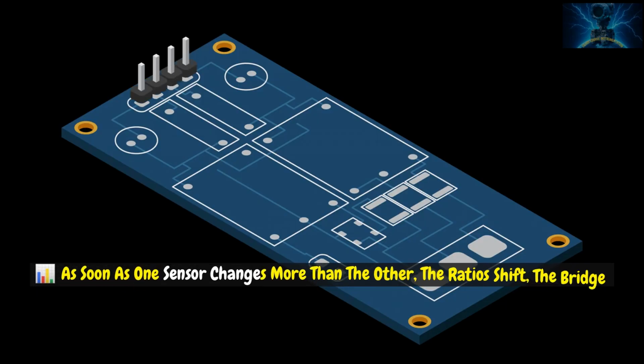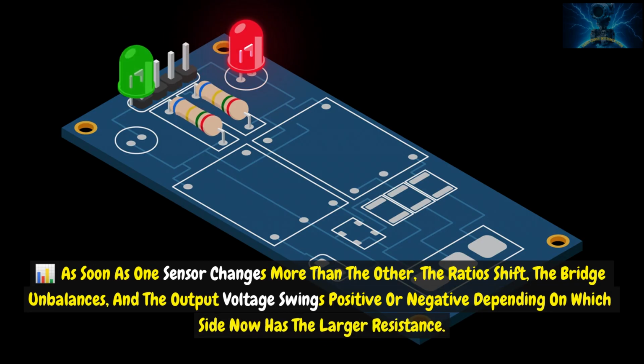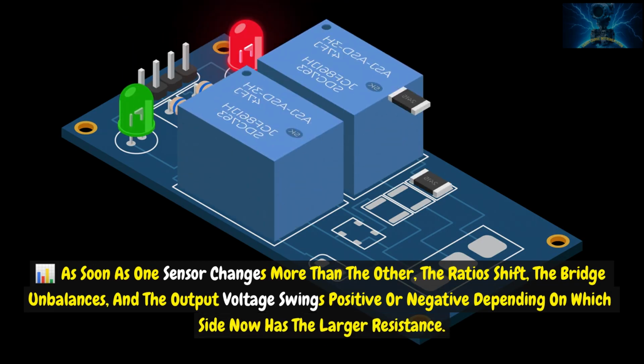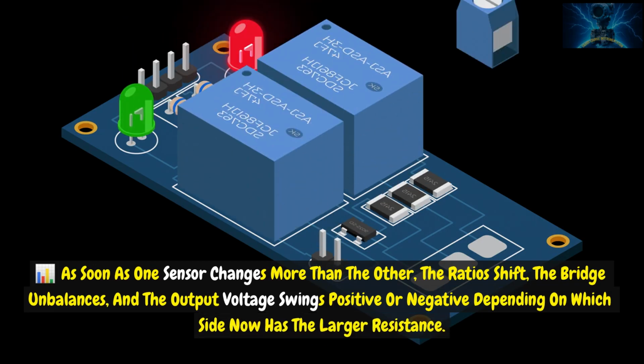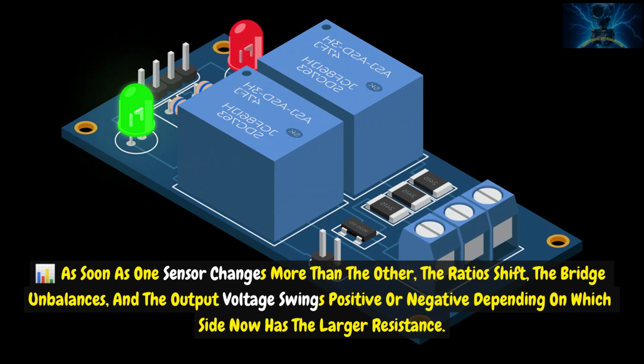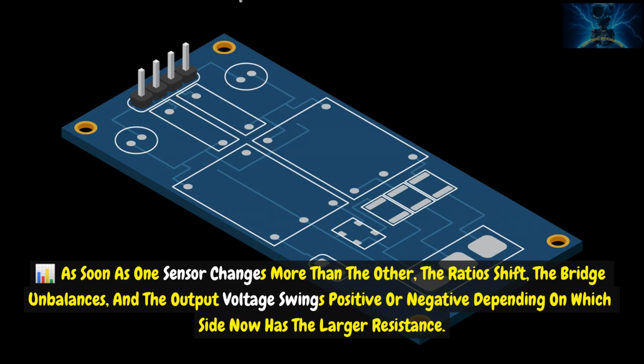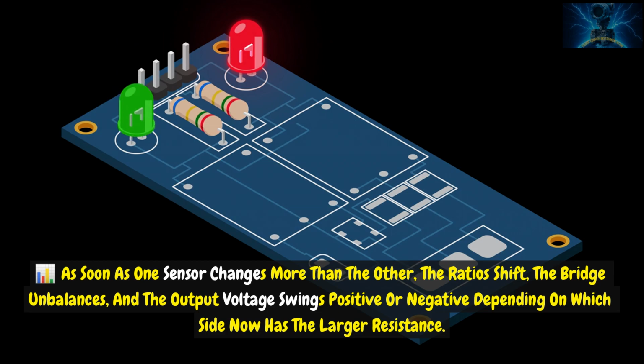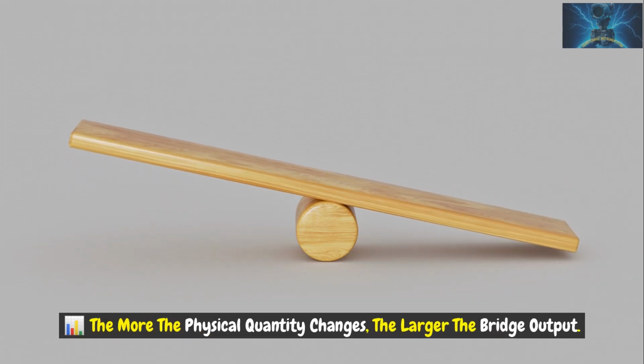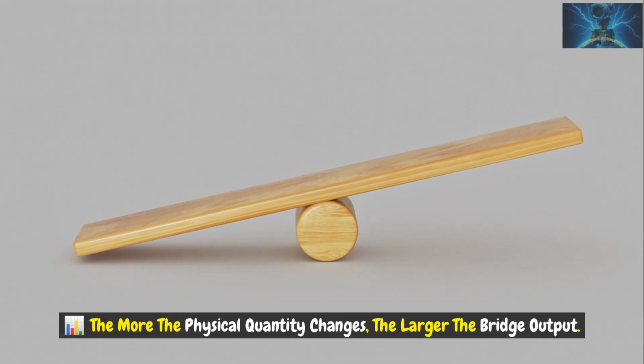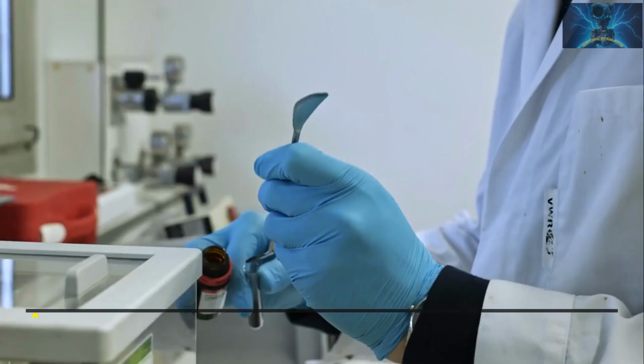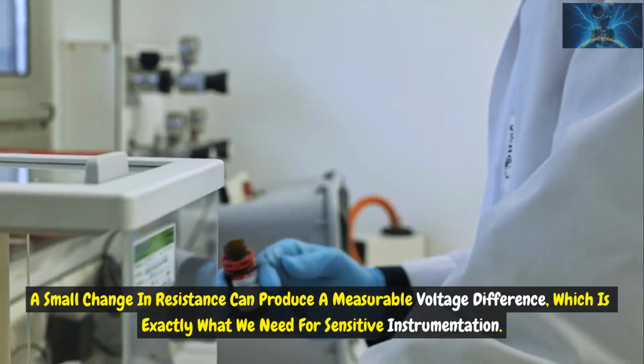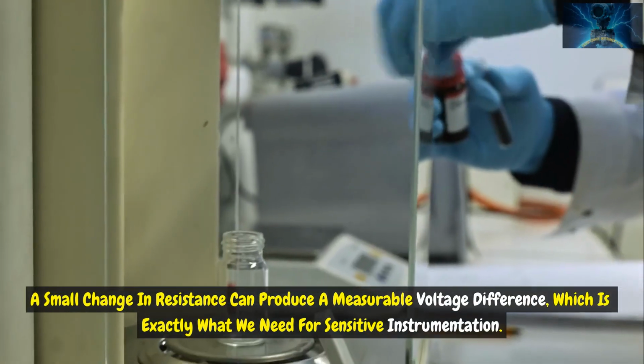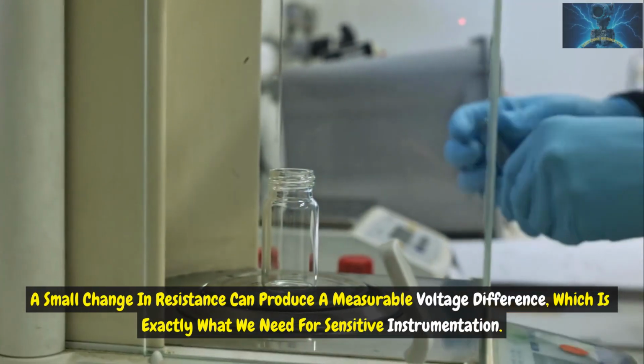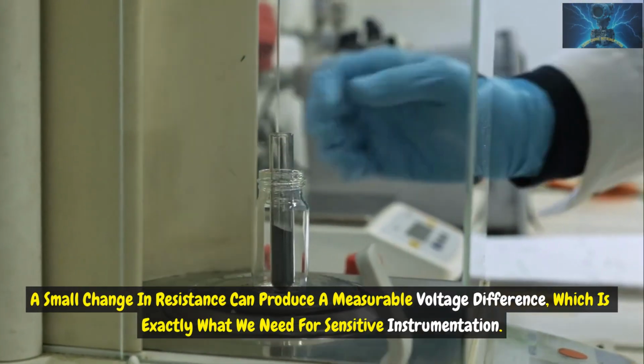As soon as one sensor changes more than the other, the ratios shift, the bridge unbalances, and the output voltage swings positive or negative, depending on which side now has the larger resistance. The more the physical quantity changes, the larger the bridge output. A small change in resistance can produce a measurable voltage difference, which is exactly what we need for sensitive instrumentation.